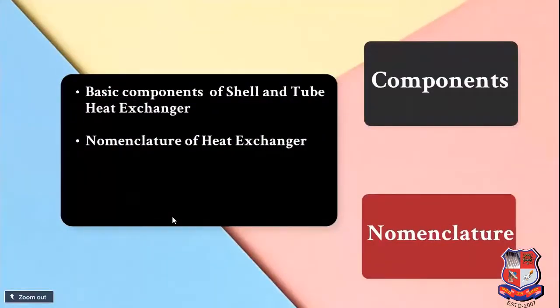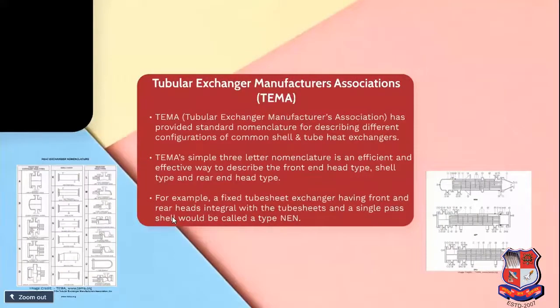Now we will move on to the nomenclature of heat exchanger. Basically, this nomenclature helps us to identify the type of heat exchanger it is. The nomenclature of a heat exchanger is done with the help of the TEMA standards, where TEMA is Tubular Exchanger Manufacturers Association, which has provided a standard nomenclature for describing different configurations of common shell and tube heat exchangers. TEMA's three simple letter nomenclature is an efficient and effective way to describe the front end head type, shell type, and rear end head type.